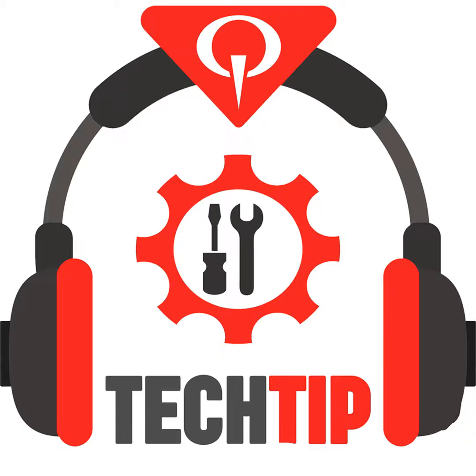And it's basically just a good idea to get started by going one by one and checking all your wiring from the camera board to your interface, from your interface to your hub, and just double checking, making sure everything's secure, everything's tight. And if you reboot it and it's still giving you the same error, that's when I would go ahead and one by one start swapping components and trying to figure out what component might be failing or causing an issue with that. So that one is something I still would recommend getting some advice on. So don't be afraid to call us still, because that's the one that usually customers need the most help with.